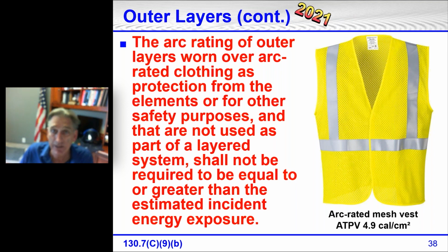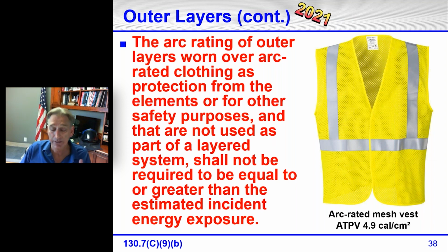Last Friday, I was teaching an electrical contractor in northwest Mississippi, and I was wearing that shirt. Of course, it was probably blinding through all the classroom portion, but when we did the hands-on portion, it was arc rated, so I didn't have to put on any coverall or anything because I was already wearing arc rated clothing. So, your outer clothing, as long as it has an arc rating, does not have to equal or exceed the prospective arc rating of the equipment that you're in front of.